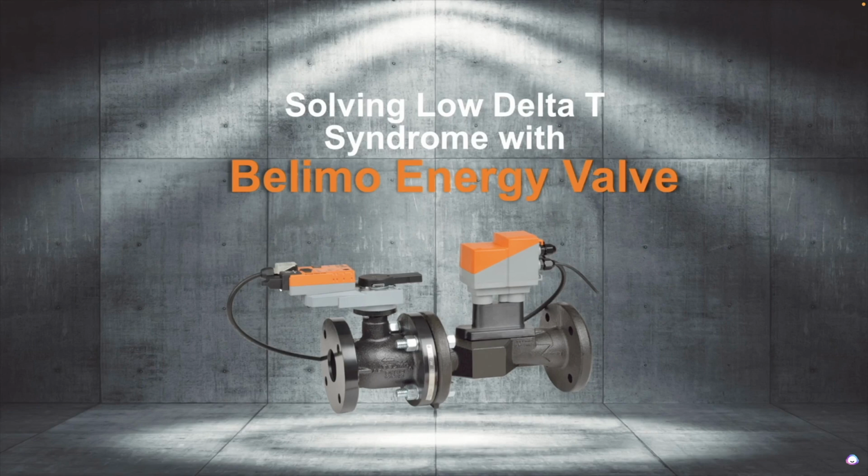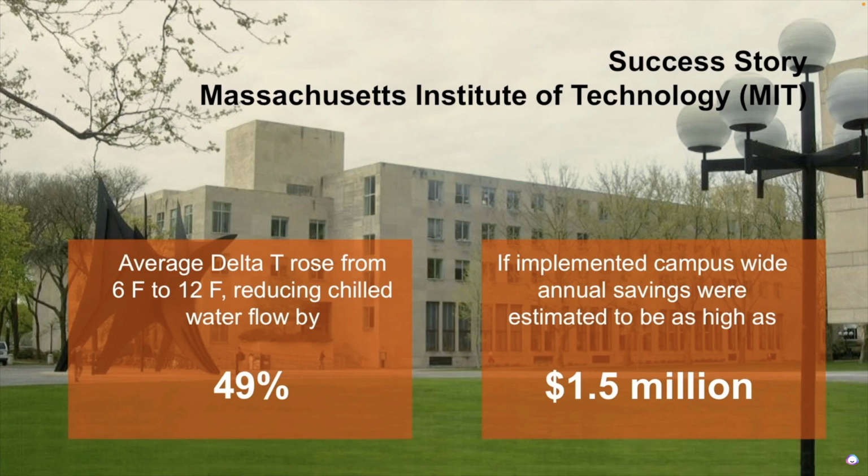It's called the Belimo Energy Valve. The Belimo Energy Valve has been used very successfully in the past in controlling delta T with some very interesting clients. The first one that we have is the Massachusetts Institute of Technology. They had a delta T problem in their Hayden library. We installed Belimo Energy Valves on the library, and we were able to raise their delta T from 6 degrees Fahrenheit to 12 degrees Fahrenheit.